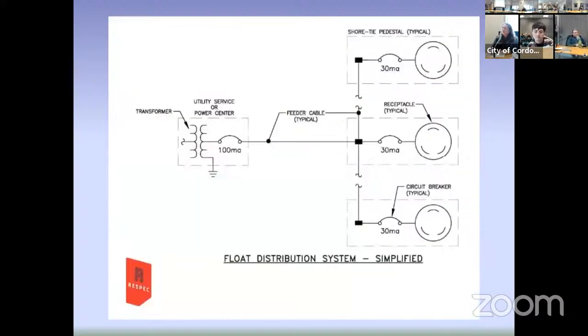Let's hit the next one. This is a very simplified representation of a harbor system. We've got the utility transformer on the left. What he was talking about is the feeder circuit breaker, which is set to trip any ground currents exceeding 100 milliamps. But you can see it's also feeding several different shore power, shore tie receptacles, which are set for 30 milliamps. Now, if you have more than three receptacles on a feeder, it's possible that you could have four leaky boats. Not likely though, but it's possible. You could have four leaky boats that will trip the main. We're going to deal with that. Let's hit the next one.